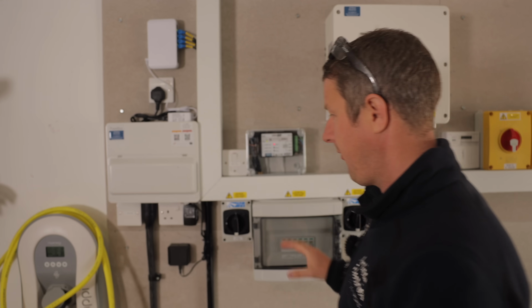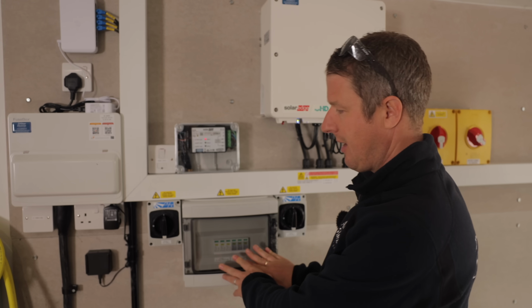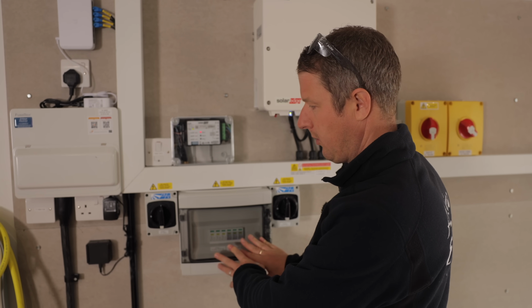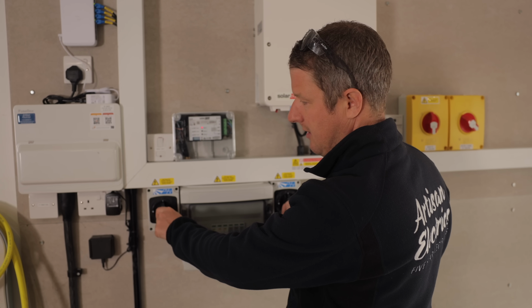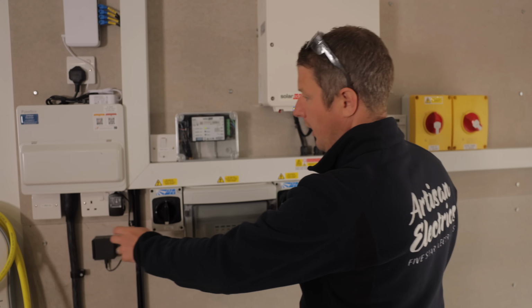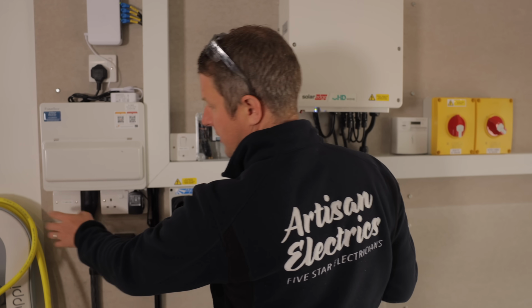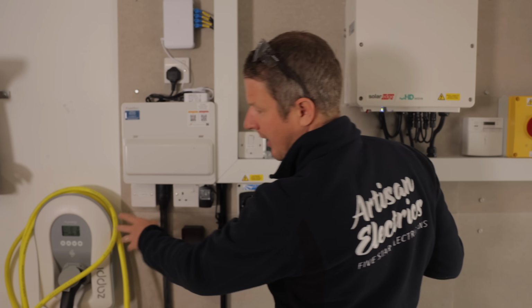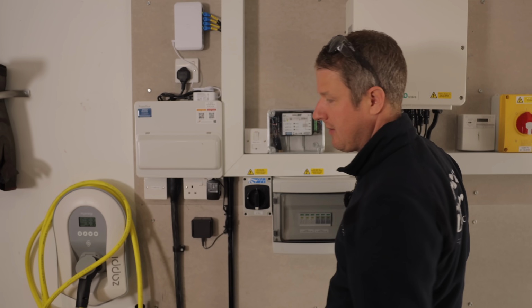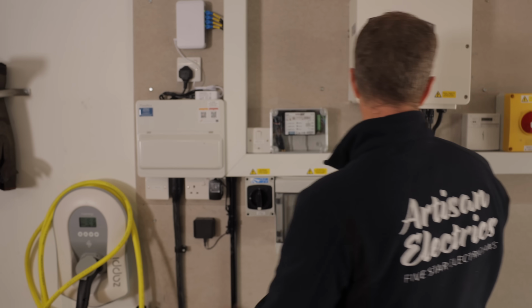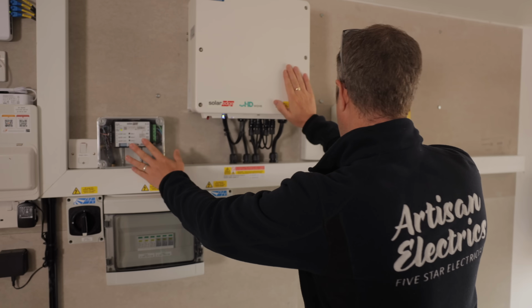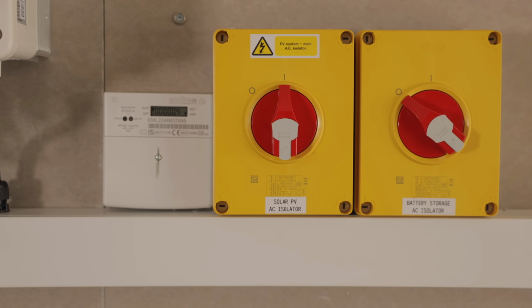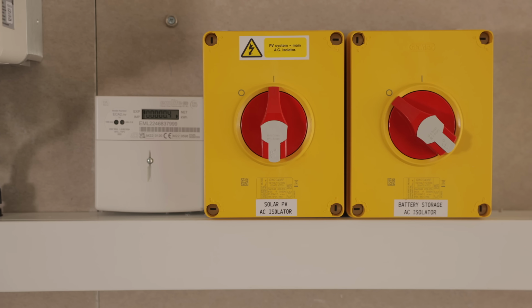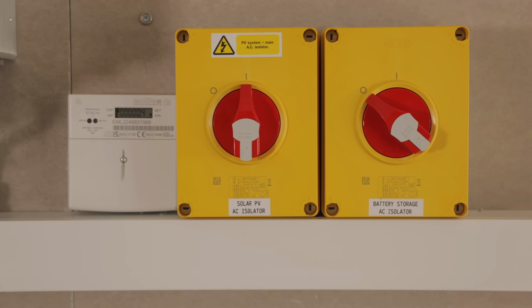Other things that we've got in this system: DC surge protection for the strings of the solar panels on the roof, 2 DC isolators, 1 for each string. We've got a little junction box here for all our CT connections. We've got a Zappi, which is existing, and we're going to get that firmware updated in a minute so that it'll talk well to the Libbi. This is our SolarEdge inverter and Modbus. We've got a generation meter and an AC isolator to isolate the SolarEdge inverter there.